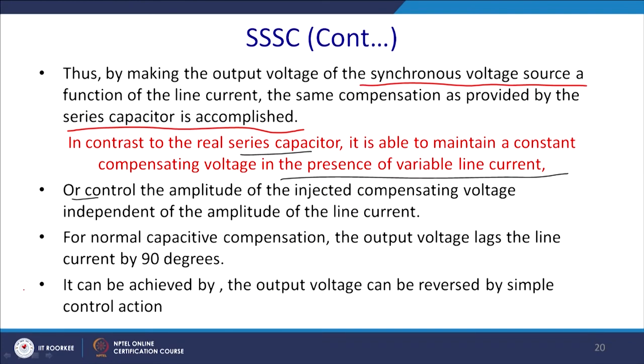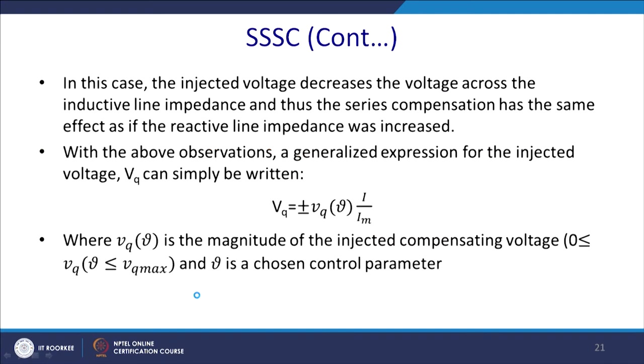We can control the amplitude of the injected compensating voltage independent of the amplitude of the line current. For normal capacitive compensation, the output voltage lags the line current by 90 degrees. By reversing the control action, the injected voltage decreases the voltage across the inductive line impedance, and thus the series compensation has the same effect as if the reactive line impedance was increased.